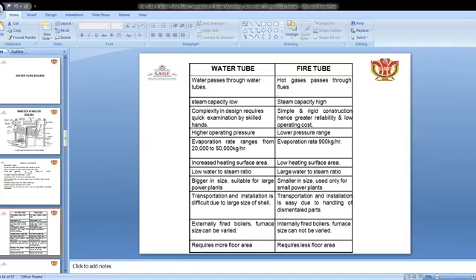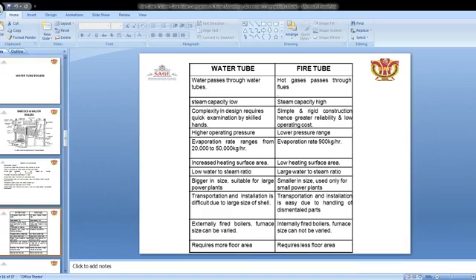Water tube boilers have an increased heating surface area with low heating surface area in fire tube boilers. Water tube boilers operate on a low water-to-steam ratio, while fire tube boilers have a large water-to-steam ratio. Transportation and installation is difficult for fire tube boilers due to the large size of the shell, but easy for water tube boilers. Water tube boilers are externally fired so furnace size can be varied, while fire tube boilers are internally fired. Fire tube boilers require more floor area; water tube boilers require less floor area.